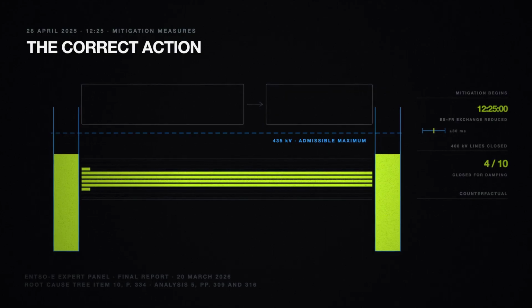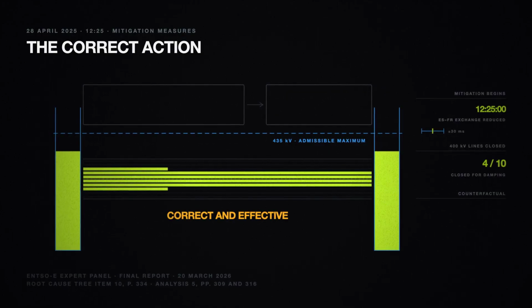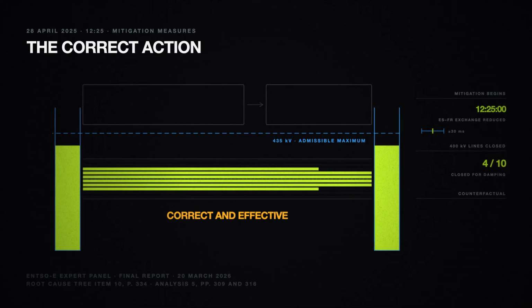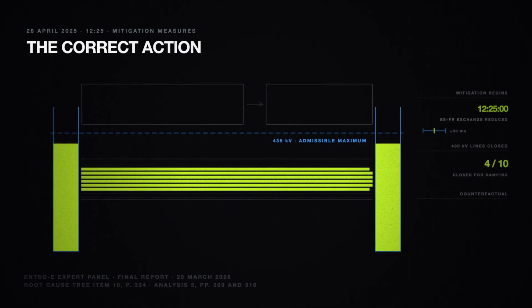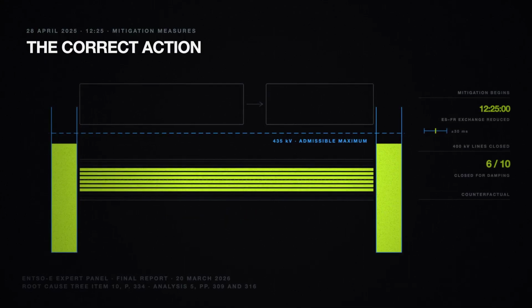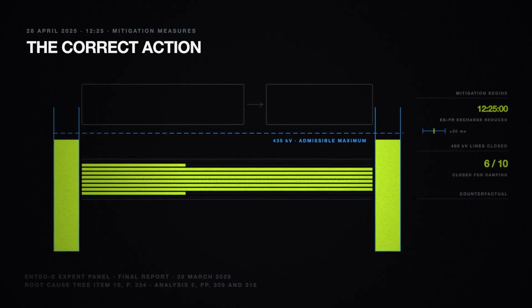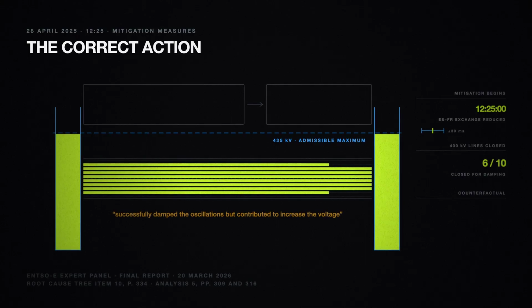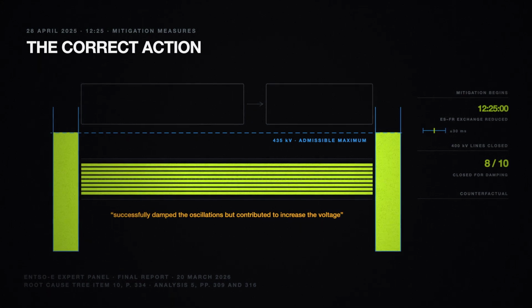The panel's assessment of the maneuver itself is 2 words, correct and effective. And then the same item finishes its sentence. On the day of the incident, the dispatchers implemented mitigation measures during both oscillatory episodes, which successfully damped the oscillations but contributed to increase the voltage.